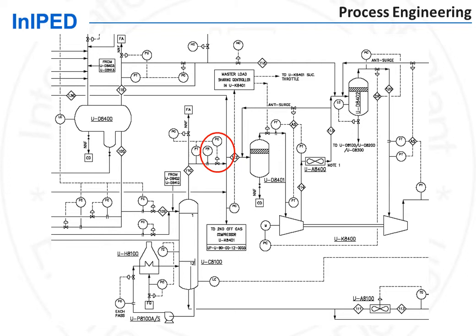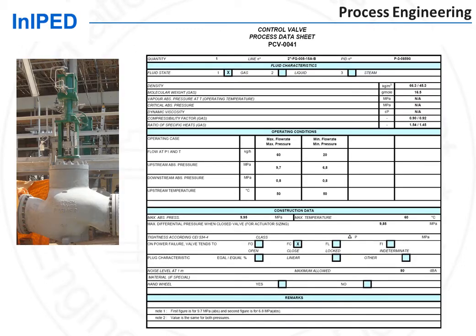Process must provide information on the control valves in order that they are properly sized by the vendor to cover the entire operating range. This is done by issuing the instrument process datasheet. The process datasheet of a control valve indicates the extreme operating conditions for the valve, so that the valve vendor can select the proper size so that the valve will effectively control over the full operating range. Usually that means that the valve is not less than 20% open and not more than 80% open. 20% to 80% is the effective valve control range.